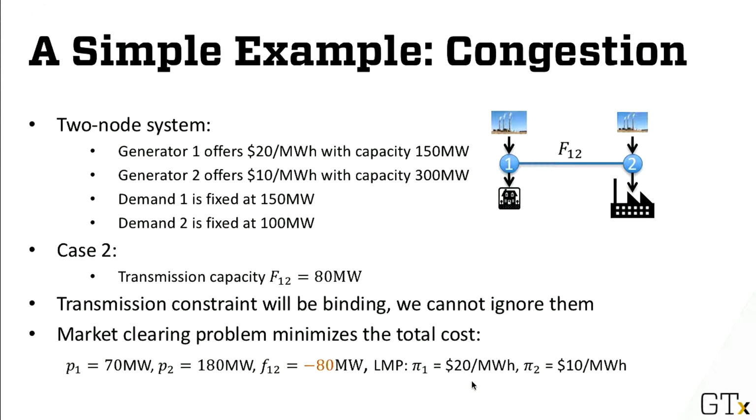So that is a higher price. Okay? And this example actually shows the intuition, the important observation that when there is transmission congestion, when the system is limited in how the flow can be transmitted, then there will be a differentiation of price in different locations because cheaper energy cannot be supplied to the demand center where the demand is as freely as possible.